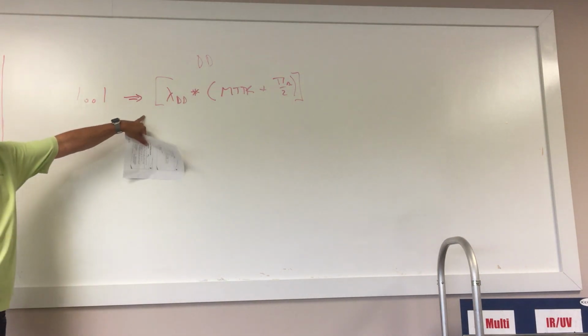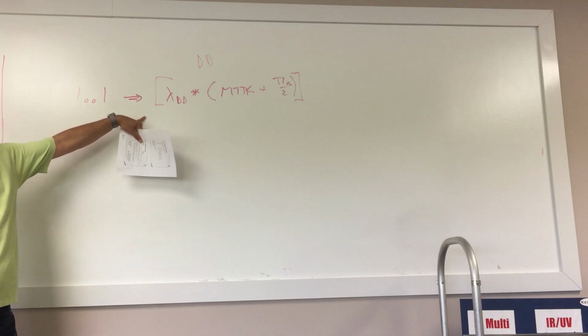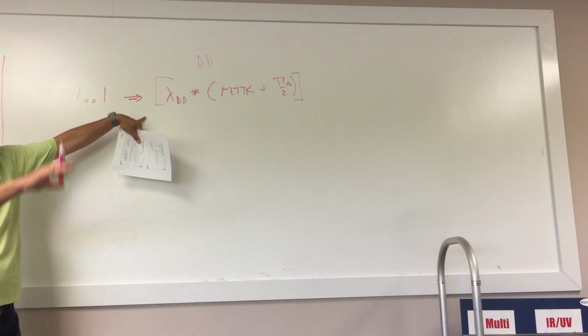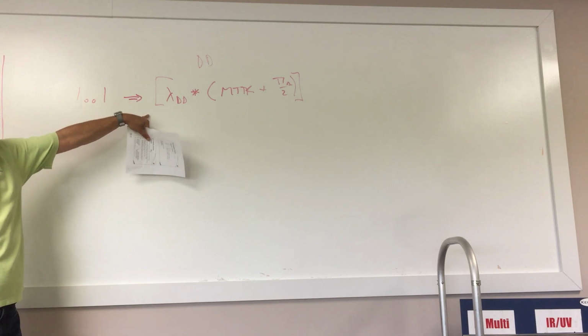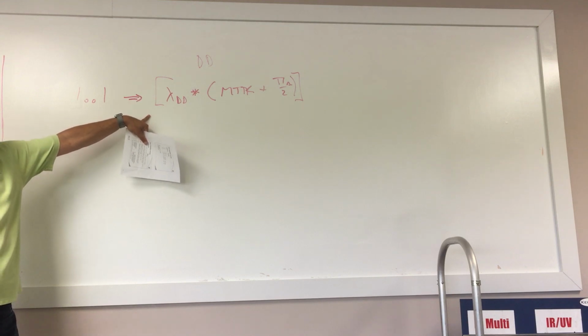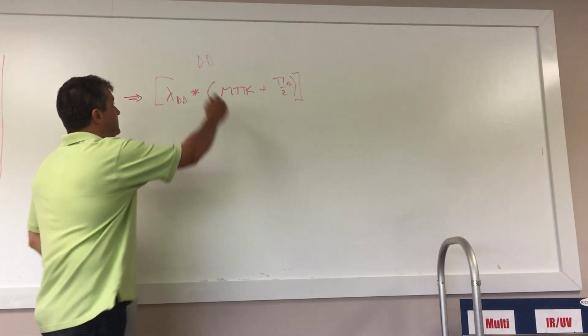And what it represents is the unavailability of the safety instrumented function, or the component of the safety instrumented function, because it has failed in a dangerous way, but that dangerous failure has been detected, but the safety instrumented function is configured to continue to allow the plant to operate in the presence of the failure and wait for it to be repaired. So this is an unavailability of the safety instrumented system component while we're waiting for it to be repaired, the DD term.